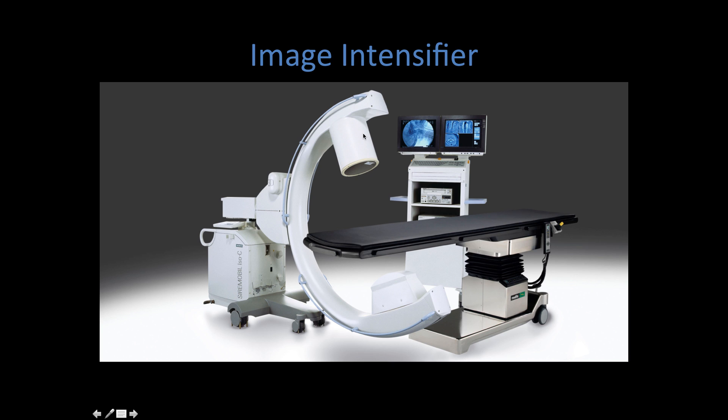The image intensifier tube has a resolution of five line pairs per millimeter, while the conversion to the TV system degrades that image to about two line pairs per millimeter. Again, this is a classic C-arm. The x-ray generator is located at the bottom. You should be able to identify the two different components of the C-arm.